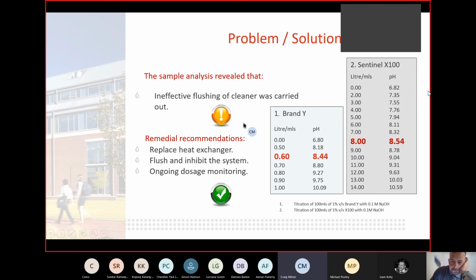You mix the inhibitor with water to the correct standard as the manufacturer specifies, then try to push the pH up to 8.5. As you can see, it only took 0.6 millilitres to push it up to 8.44. With X100, it took over 8 to push it up to 8.54. Slightly different, 8.44 to 8.54, but you can see there's a massive amount of alkaline solution that could be added to the X100 before it pushed it up to that 8.5.